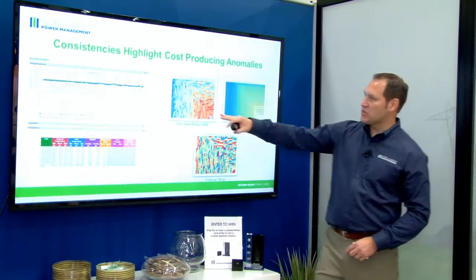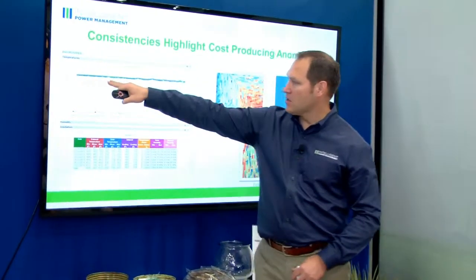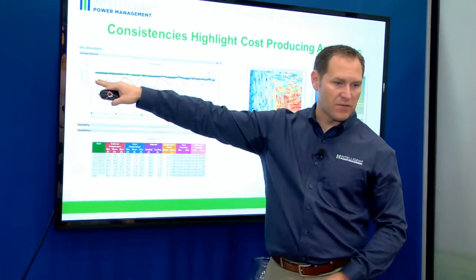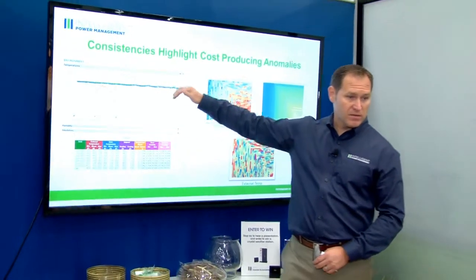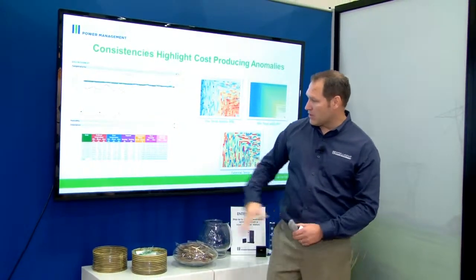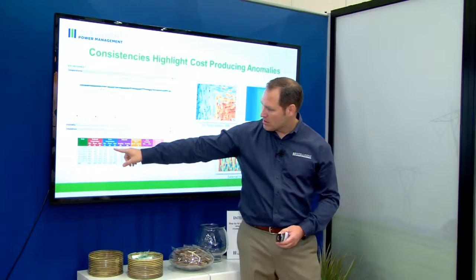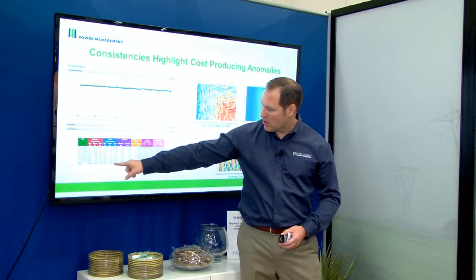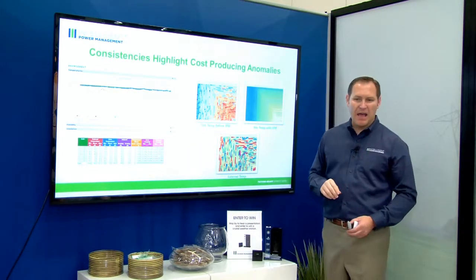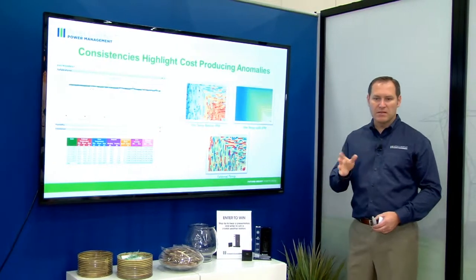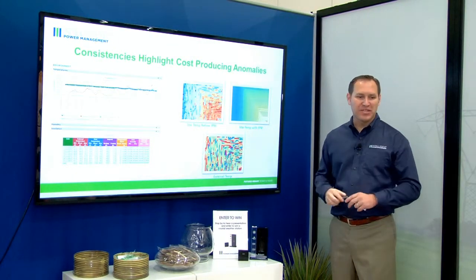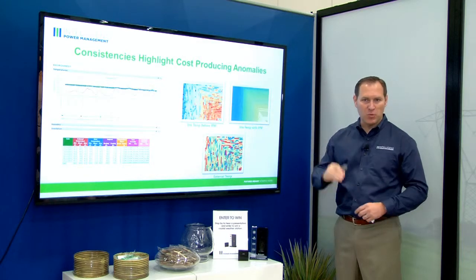Here's additional consistency data. You can see the temperature stays steady at roughly 77 degrees F or 25 degrees C — the only thing that fluctuates is outdoor temperature. They cool these shelters based on the lead-acid batteries, so the optimal operating temperature is 25 degrees C or 77 degrees F. Looking at that temperature — 77.4 all the way down — it's about a 0.5% difference between the highest and the lowest. We stay very consistent.